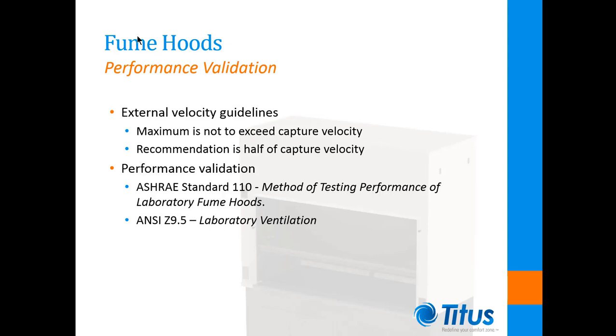There are two different standards that provide a means to determine that fume hoods are performing as intended when installed and operating within laboratories. Section 6 of ANSI Z9.5 covers commissioning and routine performance testing and is very similar to ASHRAE Standard 110. Both of these methods include airflow velocity testing, airflow visualization testing, and tracer gas containment testing, ensuring proper operation of the fume hoods within the air distribution system designed.